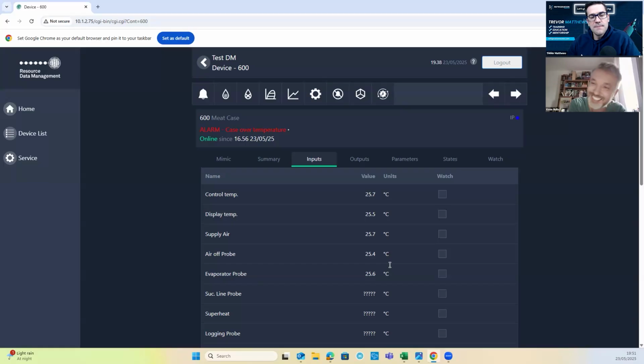I know in reality, everyone's going to push the contactor in to do it, but you do that at your peril. Yeah. And I can tell you right now, the last job I commissioned at my old place, I did exactly that. I'm no different to anyone else. And what had happened was somebody had miswired the evaporator and I had a direct phase to neutral short in the evaporator.